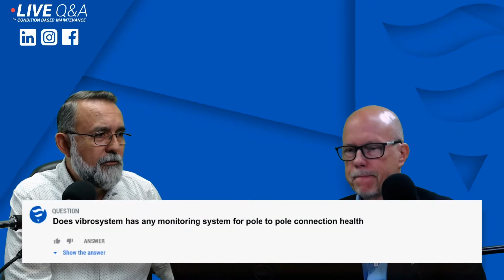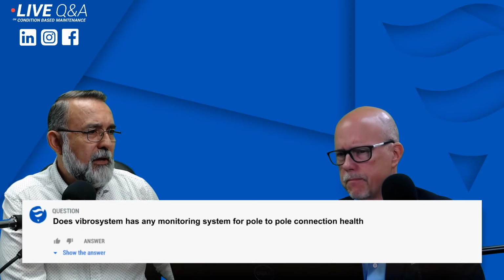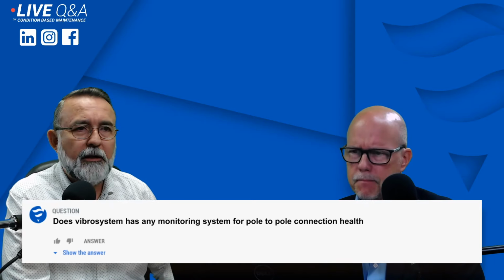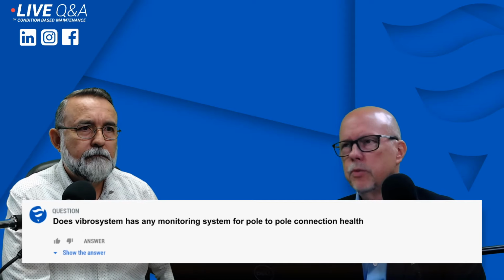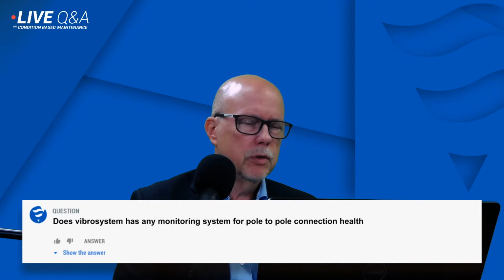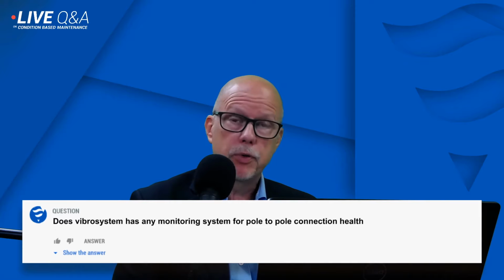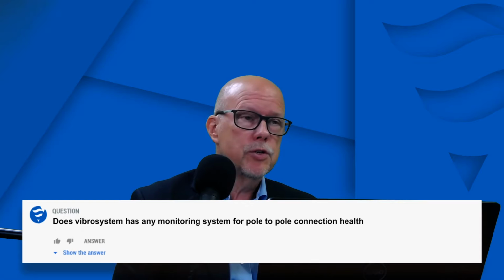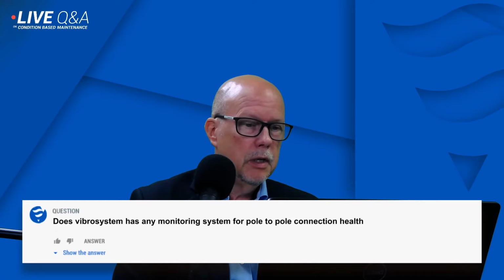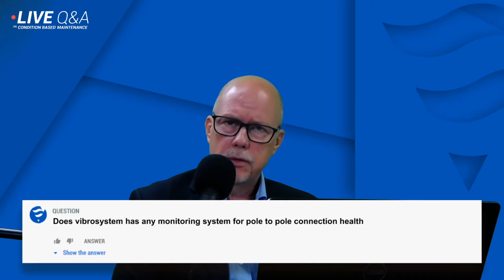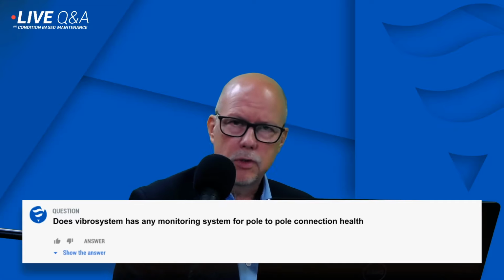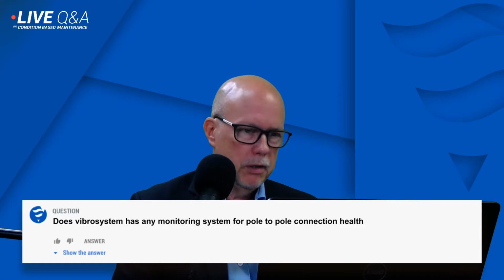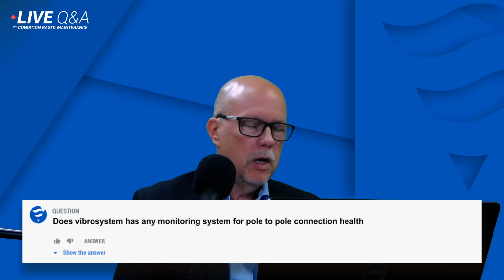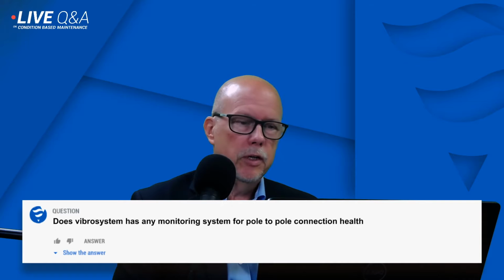And we have another question also. Does VibroSystM have any monitoring system for pole-to-pole connection health? Well, yes, we have a temperature probe, the Thermowatch Rotor, that is an infrared probe used to measure the pole face temperature. In some cases where the units are operated with new turbine technology, they're able to get an extra 4 or 5% power out of the amount of water, and that power is then transferred, of course, to the rotor and stator into electrical energy, and that usually increases the heat produced.